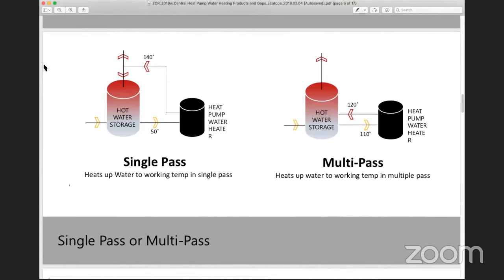you've got a higher storage efficiency, because you don't have cold water entering the bottom of a bunch of tanks, like if you were to set them up in parallel or in multipass. So when you gang a bunch of tanks together, you get a higher storage efficiency. Single pass also works and plays better with time of use and also demand response, and I'll explain a little bit of that later. Next.